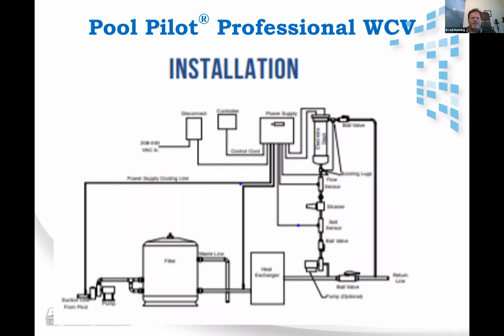This is how the installation goes. This is a water feed tube that goes up into the power supply. This is for the cooling water. All right. So it comes out of the pump, goes up inside the power supply, and returns downstream of the filter. Got to have a pressure differential there. All right. You've got your incoming power, 208 or 240. Once again, it's a 240 unit.